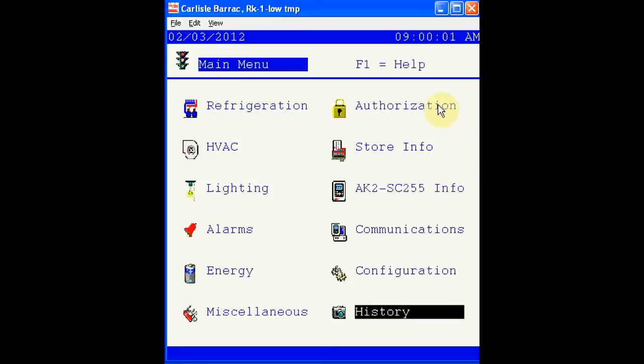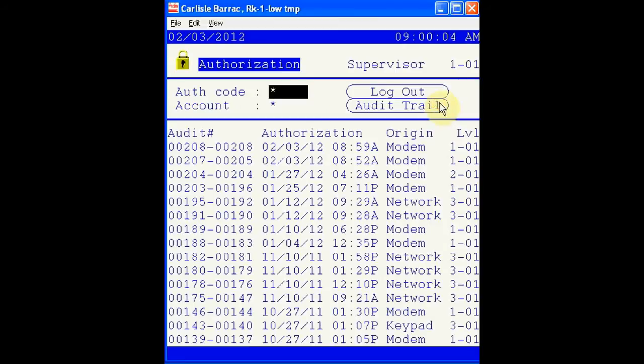Another way to log in is by going to the authorization screen. This will allow entry of your authorization code and your account code. Remember to hit enter or OK after each entry of the code or account code. It's possible to log out in this screen, and it's also possible to view the audit trail. The audit trail can be viewed without an access code and displays the contents of changes made, when they were made, who made them, and whether they were made via network, modem, keypad, or a direct connection from a laptop.